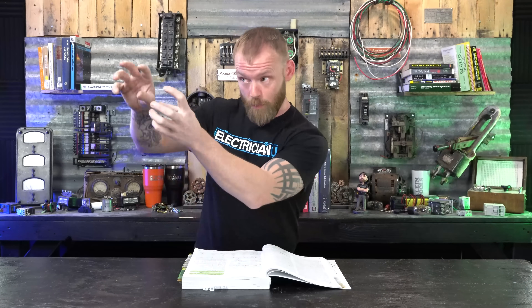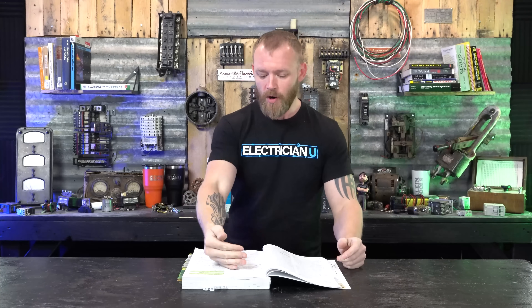If you didn't know: on a 15 amp receptacle — whether on a 15 or 20 amp breaker — you're only supposed to put a 12 amp load into any one receptacle, into any one duplex receptacle.